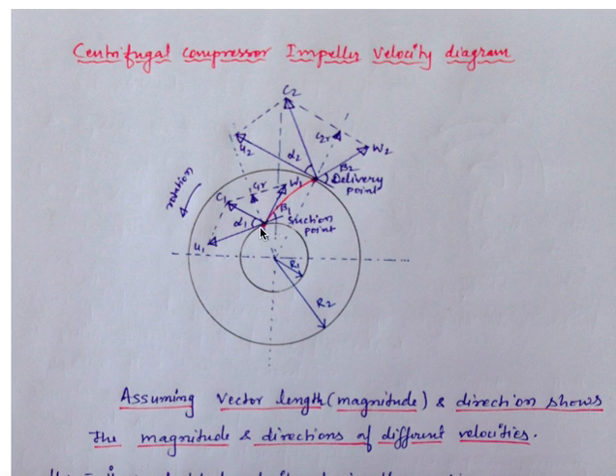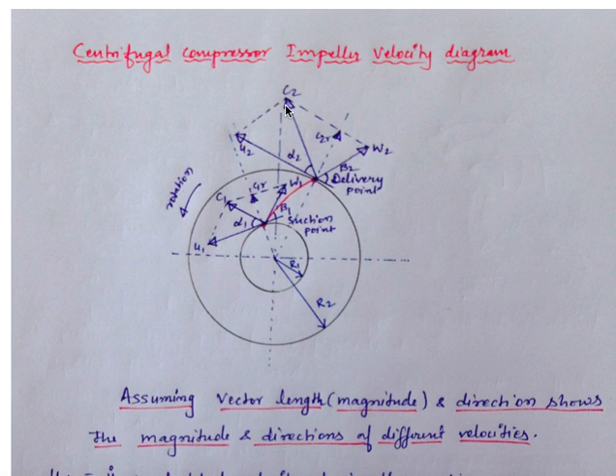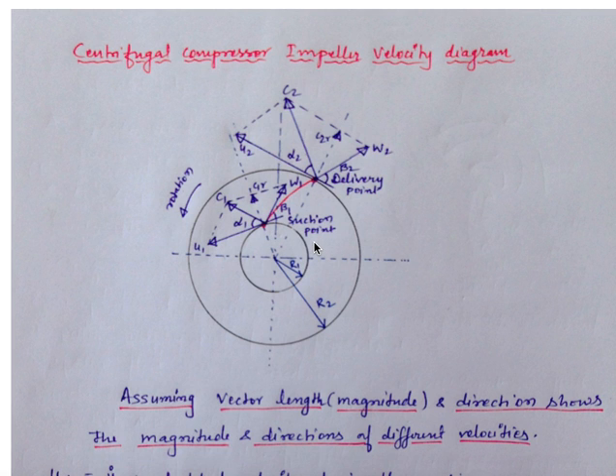Similarly, as gas moves from suction to the delivery point, we draw tangents at the delivery point and complete the parallelogram vector. The resultant at the delivery point is c2 at angle alpha2, while the suction resultant c1 is at angle alpha1. The tangent on the gas flow path at the suction point is at angle beta1, and at the delivery point it is at angle beta2. The perpendicular component of c2 on the radial direction is called the radial component of c2.